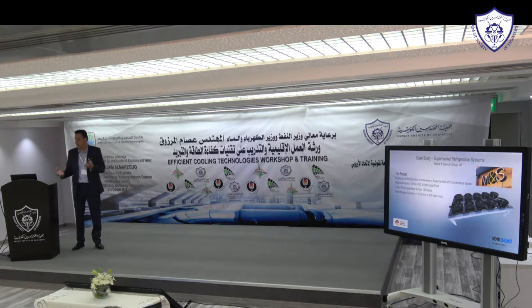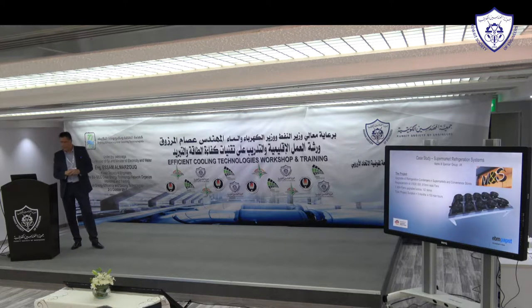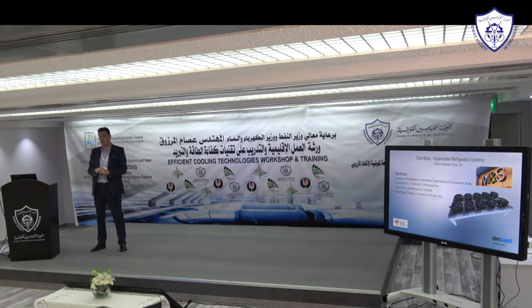The project replaced a whole variety of different types of axial fans — 630, 800, and 910 millimeter fans — all standard AC induction motor fans. There is an analogous EC energy efficient fan that drops straight in. Over a three-month period in early 2015, they carried out the upgrade.